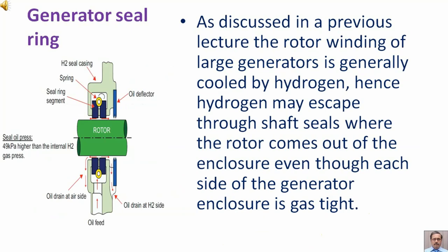As discussed in a previous lecture, the rotor winding of large generators is generally cooled by hydrogen. Hence, hydrogen may escape through shaft seals where the rotor comes out of the enclosure, even though each side of the generator enclosure is gas-tight.